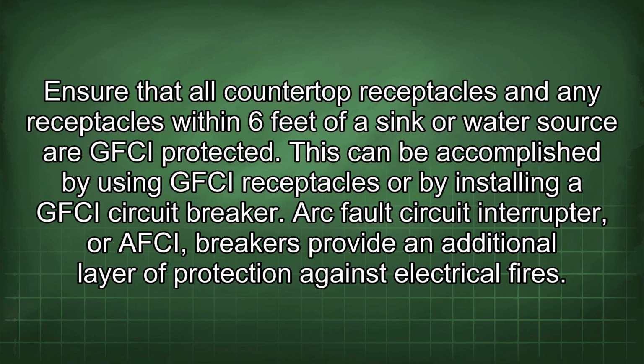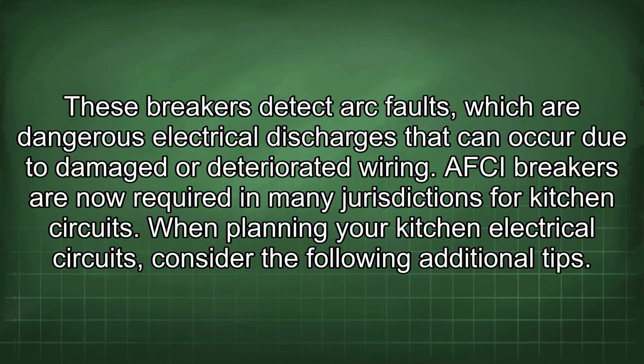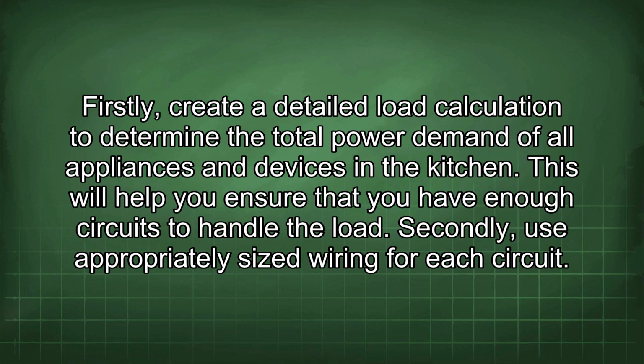Arc fault circuit interrupter, or AFCI, breakers provide an additional layer of protection against electrical fires. These breakers detect arc faults, which are dangerous electrical discharges that can occur due to damaged or deteriorated wiring. AFCI breakers are now required in many jurisdictions for kitchen circuits. When planning your kitchen electrical circuits, consider the following additional tips. Firstly, create a detailed load calculation to determine the total power demand of all appliances and devices in the kitchen. This will help you ensure that you have enough circuits to handle the load.